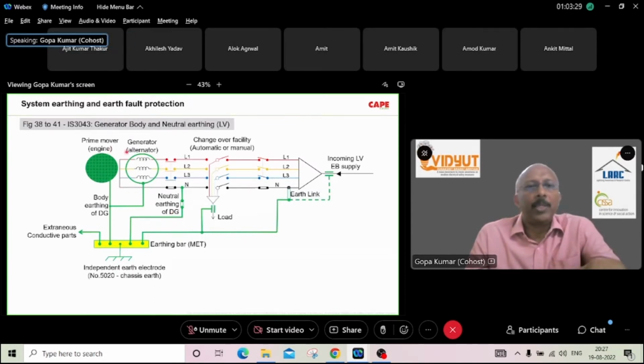Finally, I will explain how this earthing is related to fire. Now, in the picture, what you are seeing is a generator, an engine and an alternator. On the right side, you can see an incoming electricity supply. Earth link means it is a TN-C-S network. What you should look at: the engine and the alternator are both connected to a common bus bar. Neutral of the alternator is also connected to the same bus bar. Incoming EB supply, the earth is also connected to the same bus bar. Load side, again connected to the same bus bar. The same bus bar is also connected to extraneous conductive parts. Again, it is also connected to an independent earth electrode, and the chassis earth.